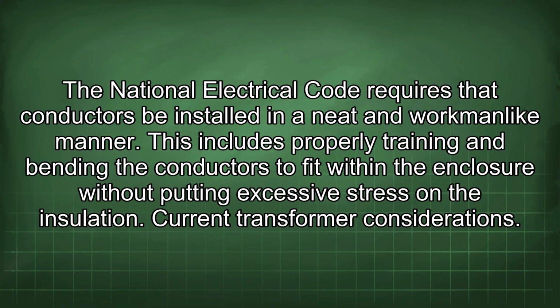The National Electrical Code requires that conductors be installed in a neat and workmanlike manner. This includes properly training and bending the conductors to fit within the enclosure without putting excessive stress on the insulation.